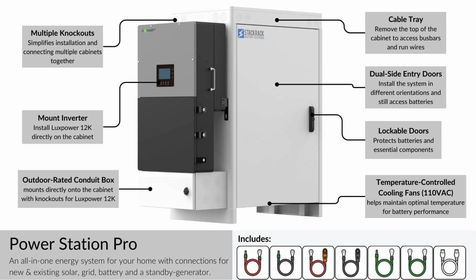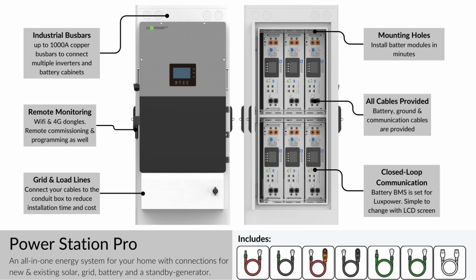There's lockable doors, and there's temperature controlled cooling fans to maintain optimal temperature inside the cabinet. We have industrial bus bars in the top of the cabinet up to 1,000 amps. This really comes into play for light commercial or larger homes where you want to parallel multiple cabinets together and use multiple inverters. There's options for remote monitoring, Wi-Fi, and 4G dongles. The outdoor rated conduit box allows for grid and load lines to easily come in and attach. From the battery side, there's mounting holes to allow you to slide the batteries in and secure them very simply with the hardware that's provided.